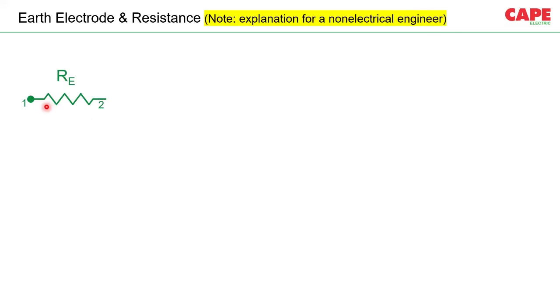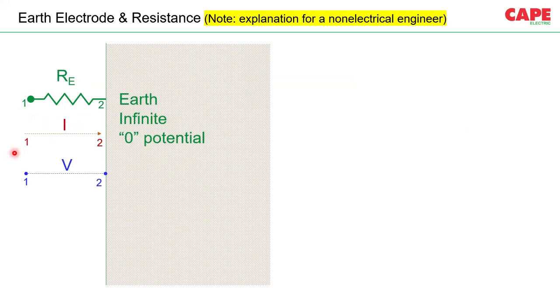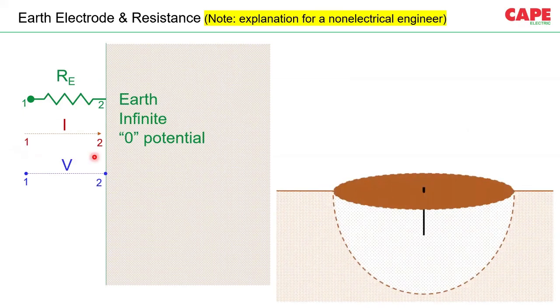I am just putting this influencing area as a resistor, for example, and on the other side you have the infinite earth, and point number 1 is the tip or the terminal of your earth electrode. So between the earth electrode terminal and the mother earth, you have a resistance, and whenever there is a current flow through this particular earth electrode, a voltage is created. Very simple to understand. Because there is a resistance and there is a current flow, a voltage is created, and the important part is this voltage will be over this particular area.